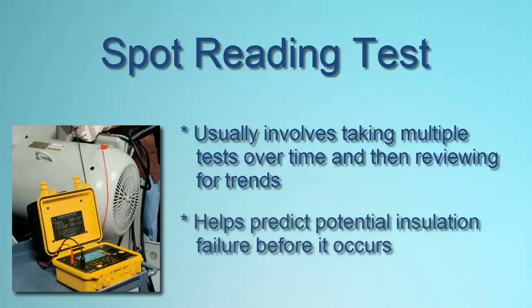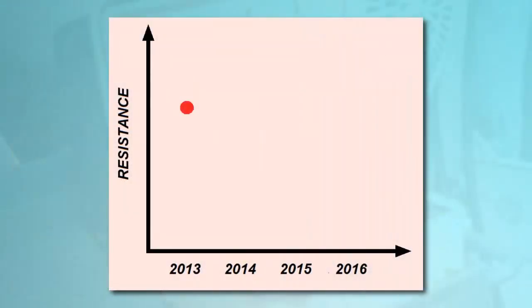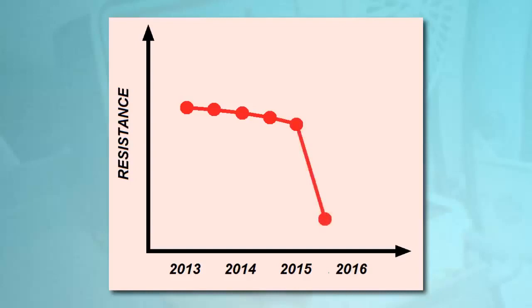This comparison can help predict a potential insulation failure in time to take corrective action. For example, suppose you perform a spot test every six months. Plotting the results on a graph, you observe a slow and gradual downward trend, as would be expected by the normal aging of insulation. However, your latest measurement reveals a sudden drop in resistance. This is likely an indication that the insulation has begun to deteriorate at an accelerated rate. To address this, you can schedule downtime for the system and take appropriate measures such as cleaning, upgrading, or replacing the insulation.